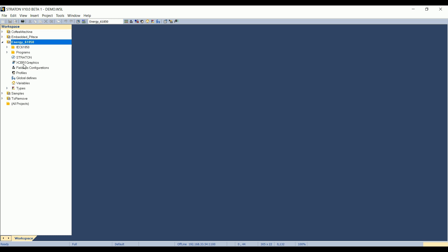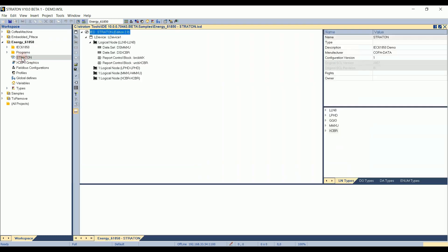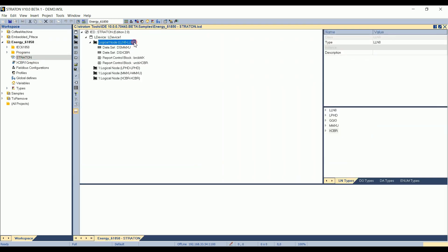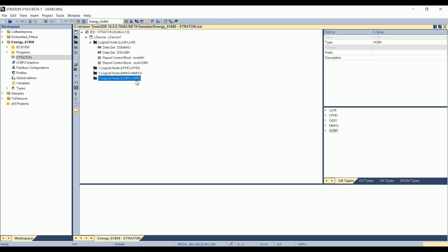We can see that in this SCL file we have four logical nodes: logical node 0, LPHD, MMXU, and a circuit breaker logical node.